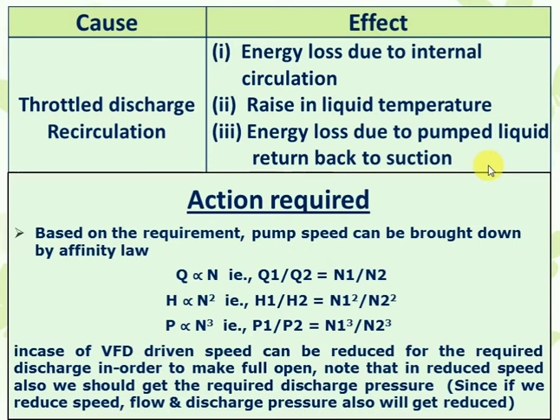So how can we mitigate and control the energy loss caused by throttling or recirculation? We need to reduce the pumping rate. To reduce the pumping rate, we can reduce the speed of the pump. If it is a VFD-driven pump, we can reduce the speed by frequency control. By the affinity law, discharge flow Q is directly proportional to the speed N of the pump.